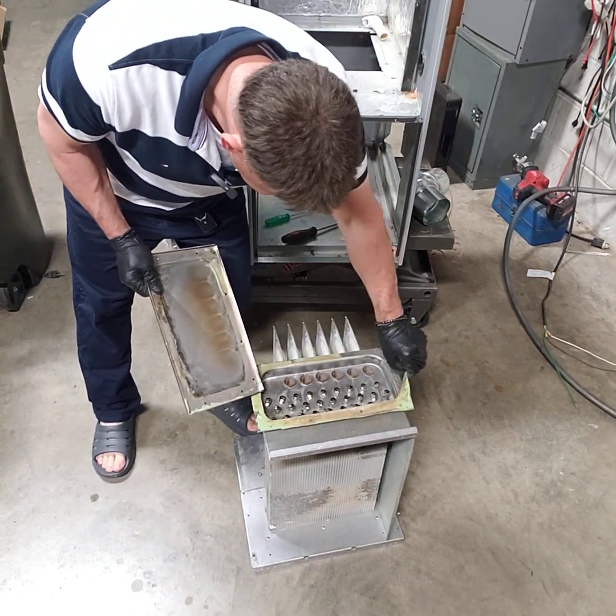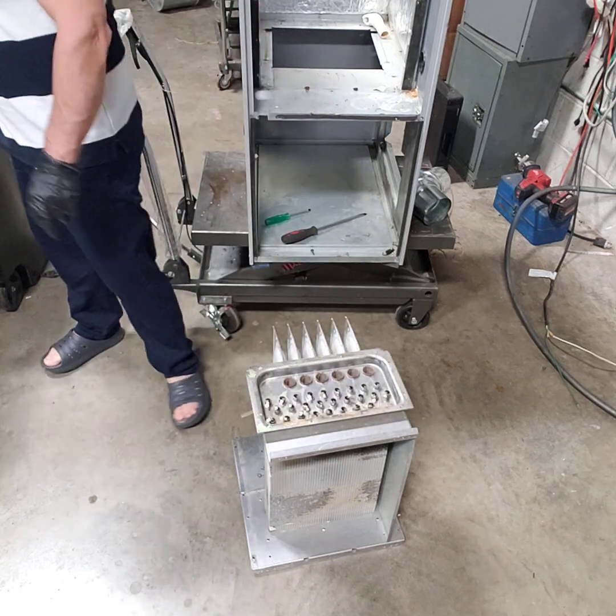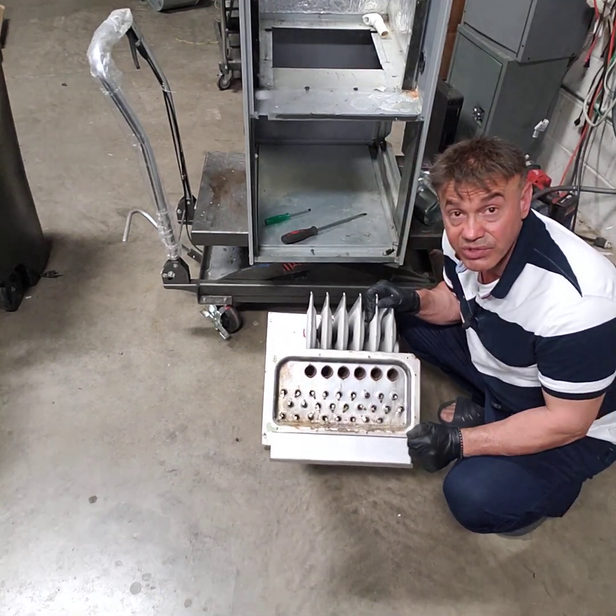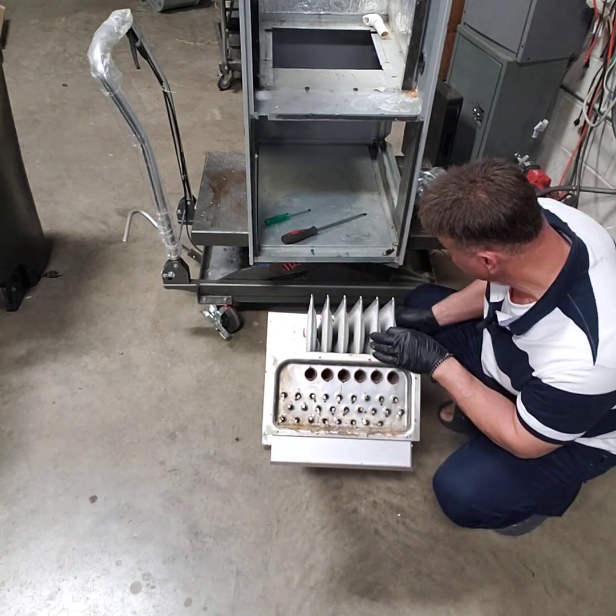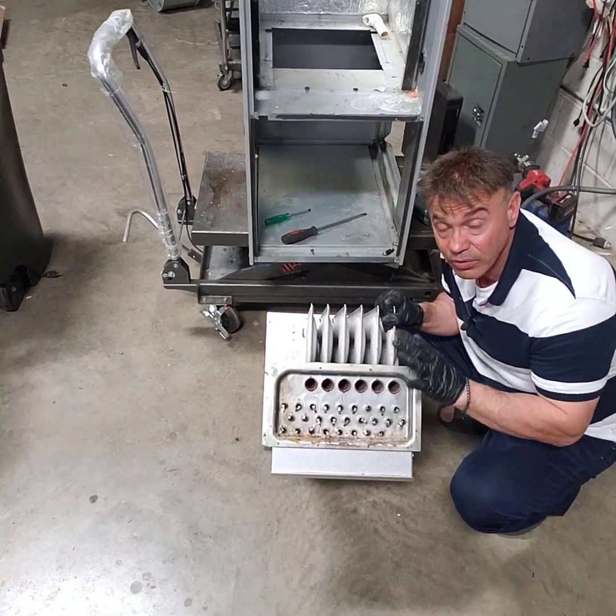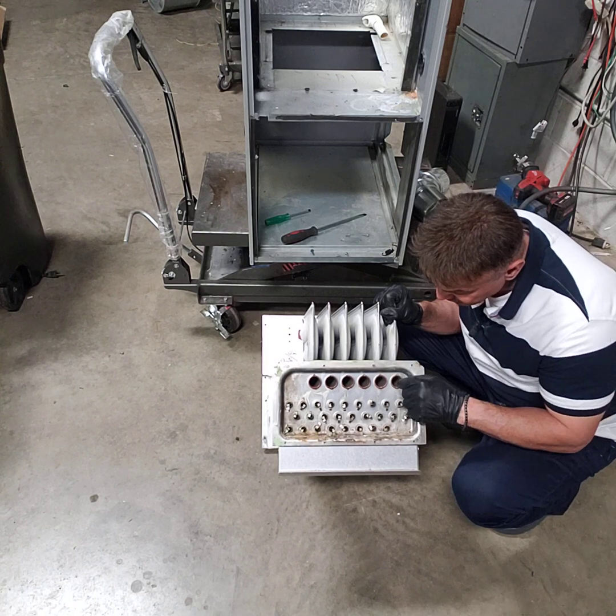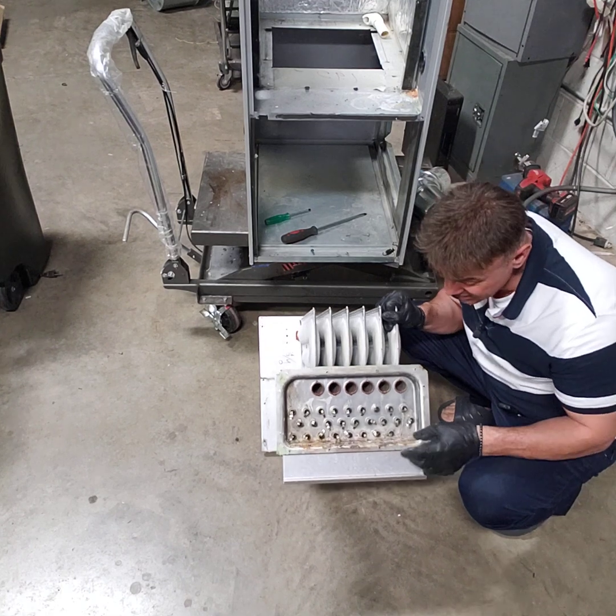See how you have to seal it. This is the mixing area, and I was telling you earlier, because of the condensation, you're gonna see a lot of rust. See, this is what happened with the high efficiency furnace. You can see it, I guess. See how when the fire comes in here, and as I was telling you earlier, remember the PVC intake, I don't recommend taking it from outside, because all this freezing air, when it's like 20 below, it will travel and cause moisture also. And you see how we do the rust here? So there's a lot to it. High efficiency is very complicated.